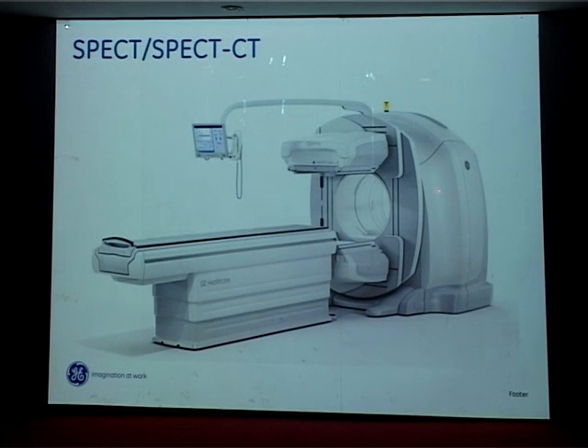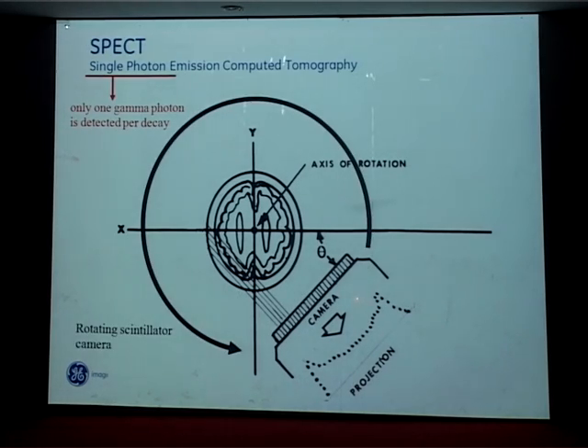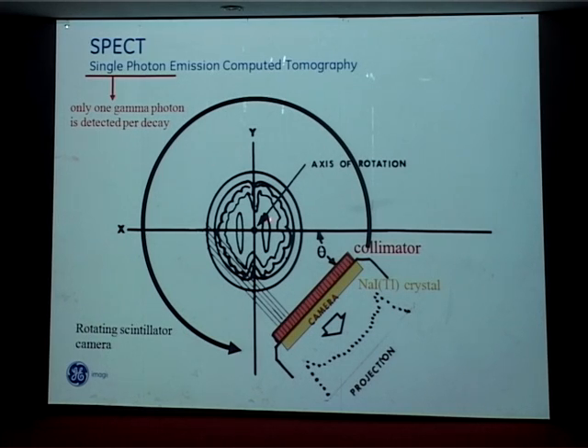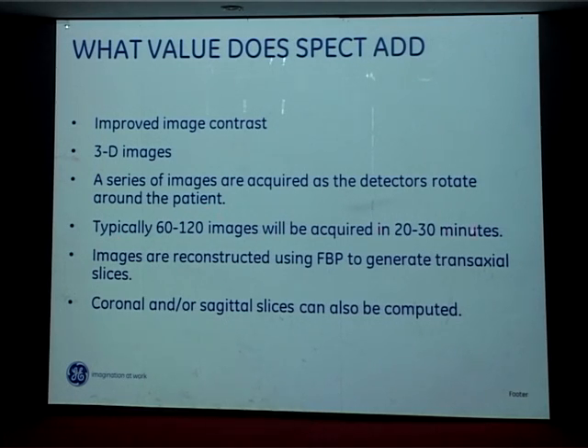A SPECT-CT machine combines a gamma camera with an attached CT scanner. SPECT — single photon emission computed tomography — detects one gamma photon per decay event. The detectors rotate around the patient, collecting images at particular points; these are then reconstructed on the computer to give an idea of activity distribution in the patient. SPECT improves image contrast and gives 3D images. A series of 60 to 120 images are acquired as detectors rotate in 20 to 30 minutes, reconstructed using filtered back projection to generate transaxial slices. Coronal and sagittal slices can also be generated.